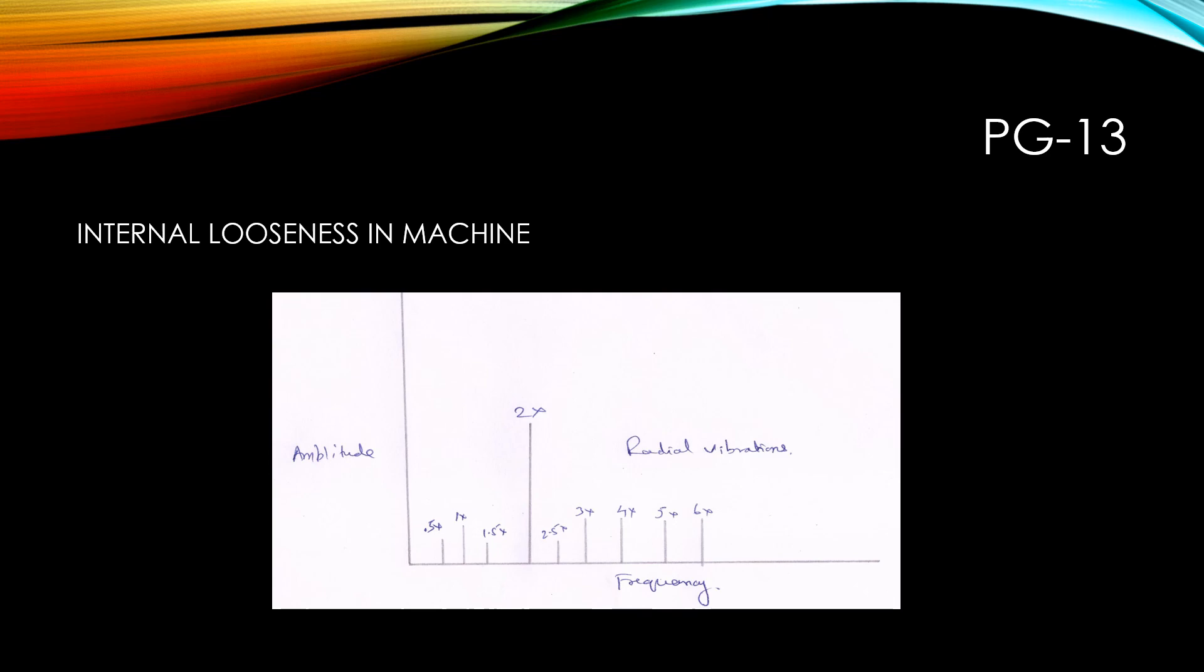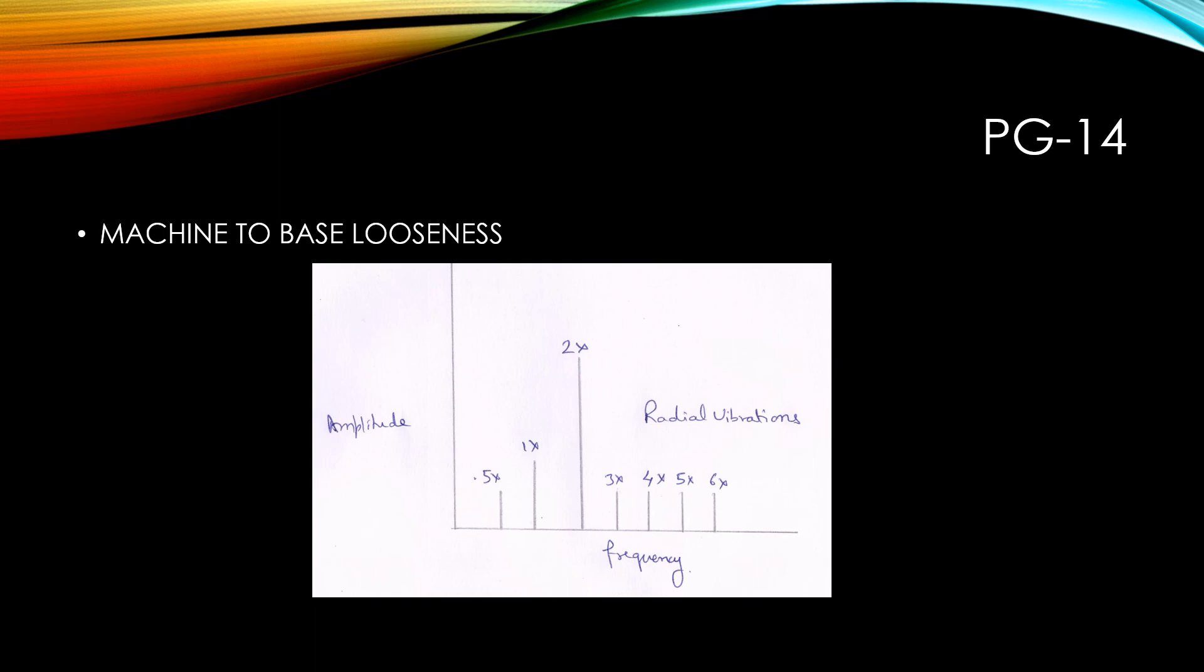So this is the internal looseness in the machine. Then, the looseness between the machine to base plate. The problem is associated with loose pillow block bolts, cracks in the frame, structure, or the bearing pedestal. This makes it evident how higher harmonics are generated due to the rocking motion of the pillow block with loose bolts.